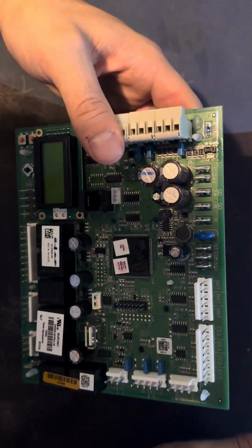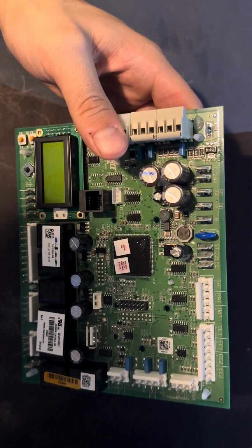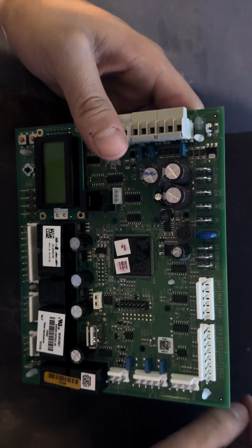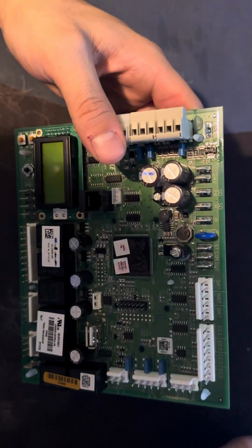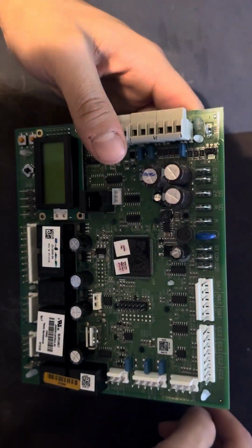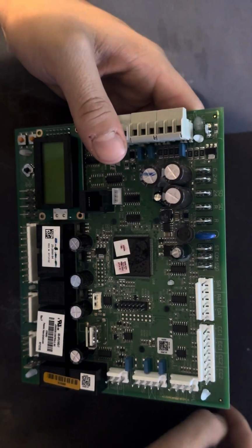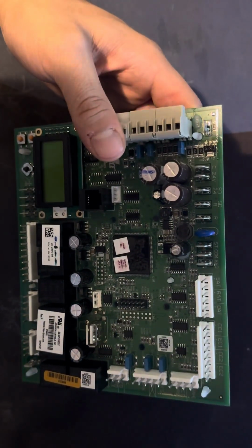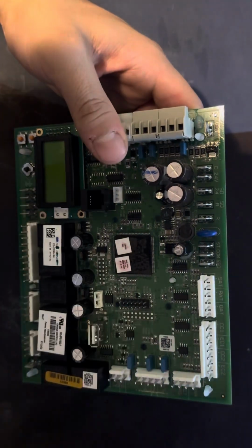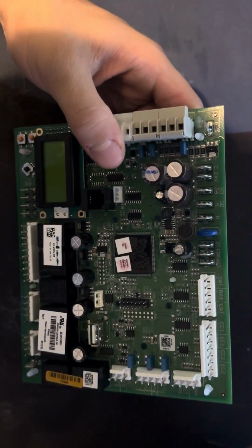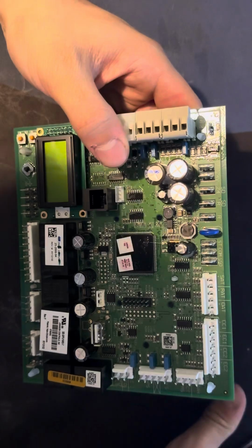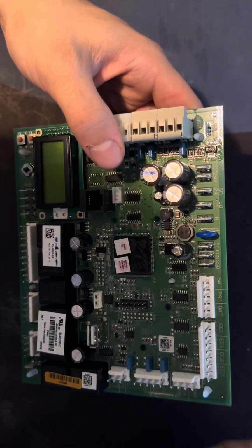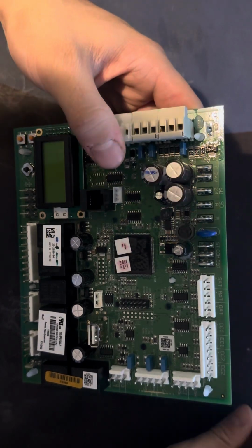Same thing can happen maybe just because you have a limit switch that's corroded, or some terminals or wire that's corroded and highly resistive, causing a voltage drop to ground, a grounded limit. Something like that could also be causing voltage drops coming back to this limit switch and causing nuisance fault trips, causing the board to lock out on HS1 off due to the limit. So if you have corroded limits, change them. Corroded wires, change them. Corroded terminals, change them.